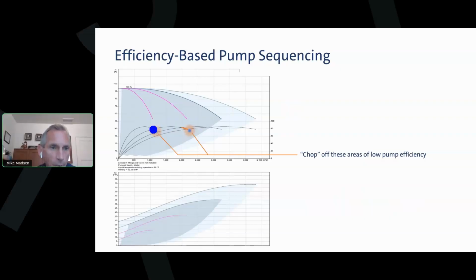And you can see right here where pump 1's efficiency drops below what the 2 pump efficiency would be. And you can see right here where the efficiency of 2 pumps drops below what the efficiency of 3 would be. We can automatically tell the pump, don't operate there. Turn on the next pump. And we can optimize the efficiency over that full operating range.